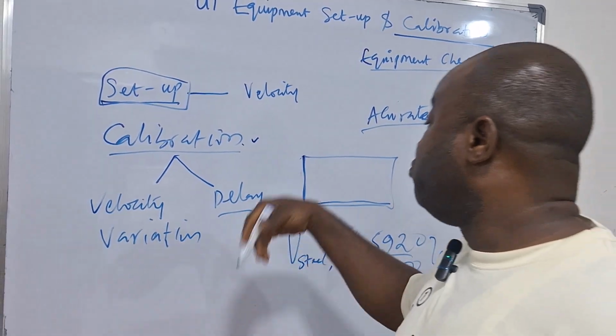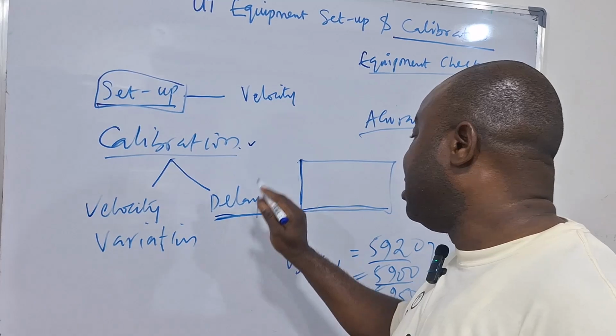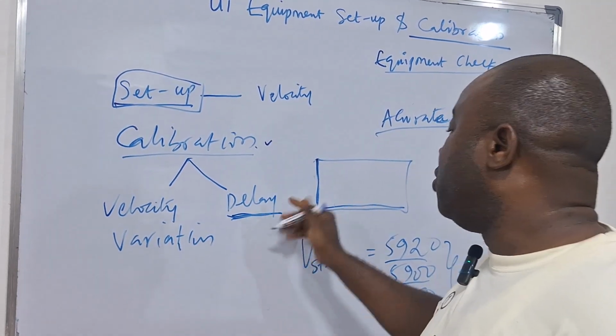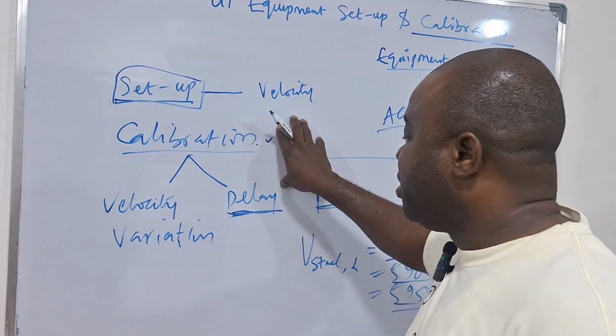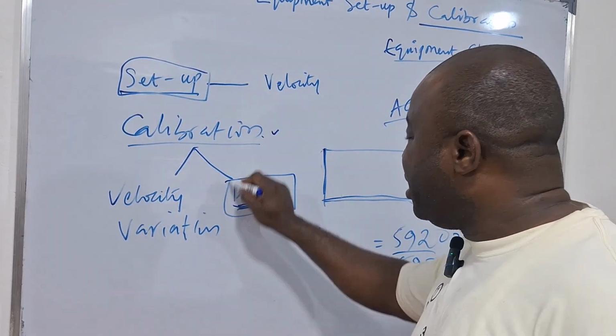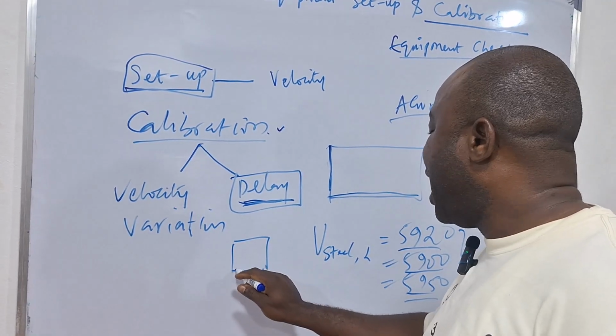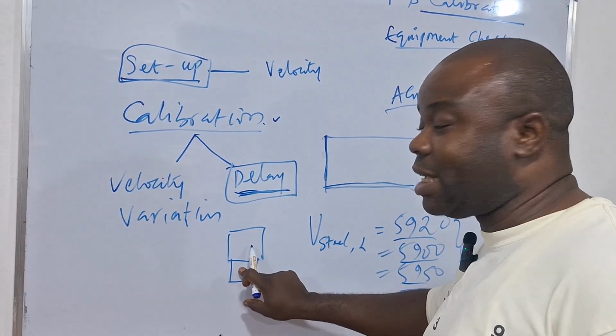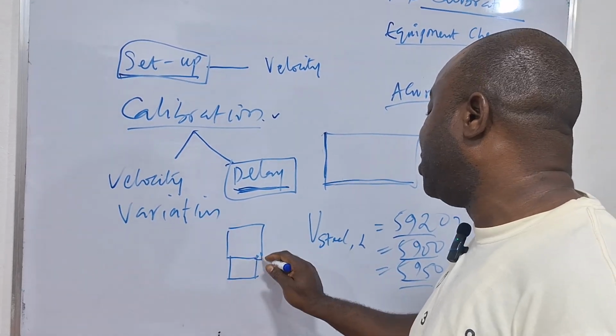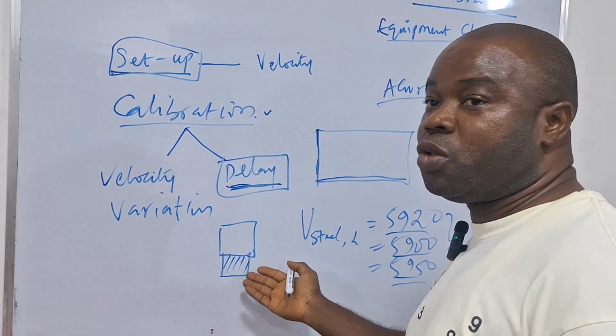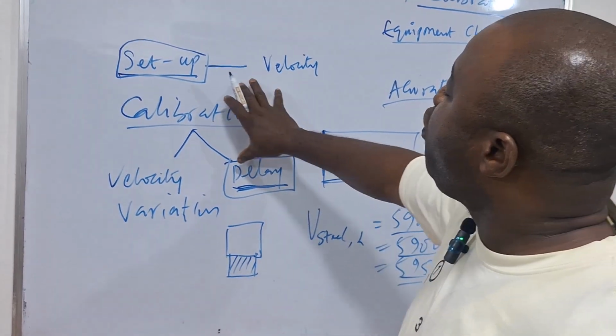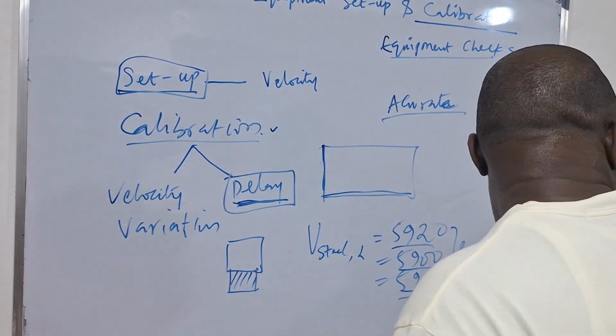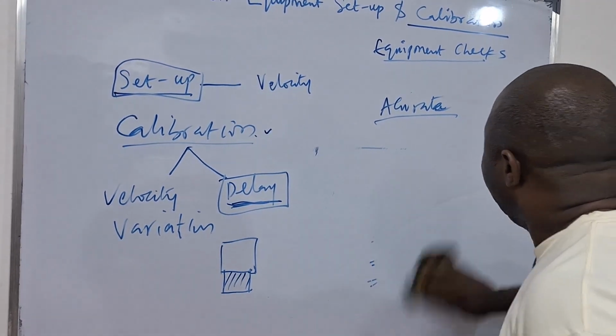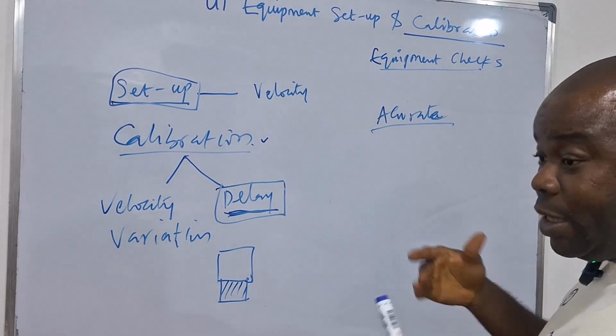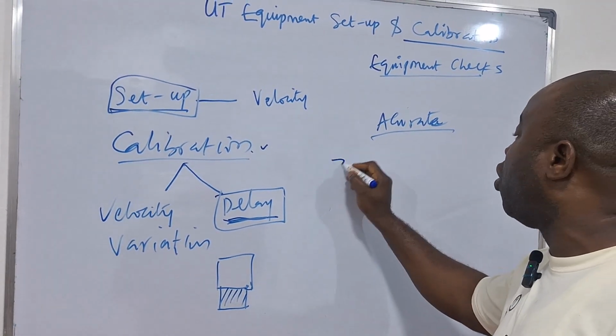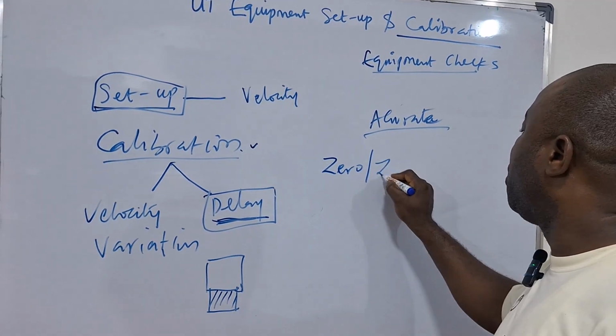So with your delay in this case now, you use this delay value to adjust your velocity variation. Then when you look at delay mainly too, some probes come with delay. So I can have a probe and have an external attachment, a Perspex, to cancel out the near field or dead zone effect. This also introduces delay, which will also affect your thickness. So when you are performing your calibration, you are going to do that with the aid of what we call the machine inbuilt delay. So it depends on the manufacturer of the equipment. Some you might have what to call your equipment zero, or some machines will call it zero delay.